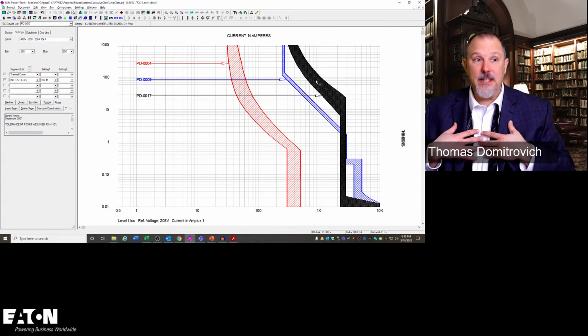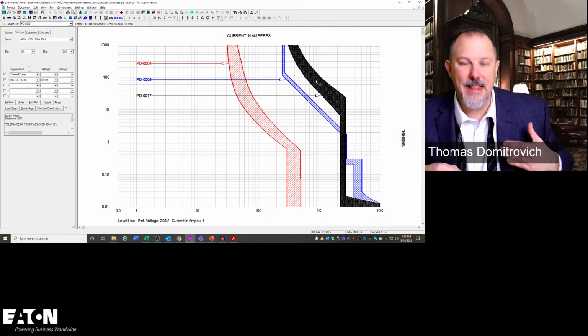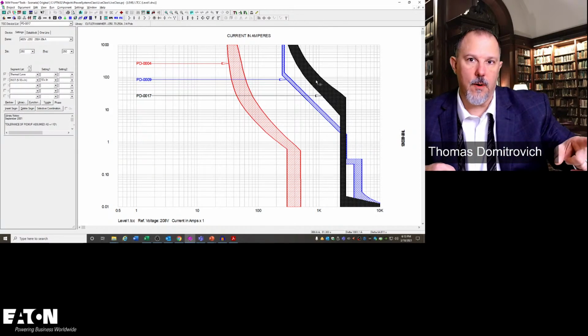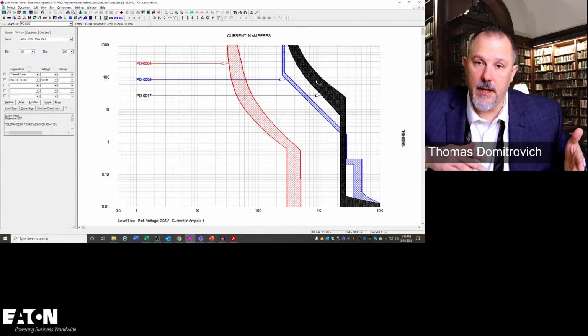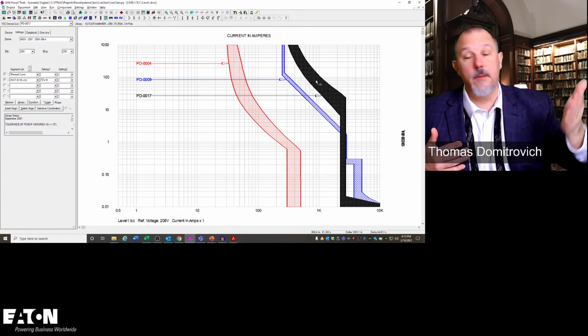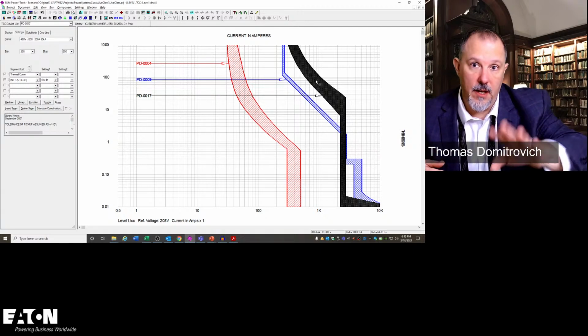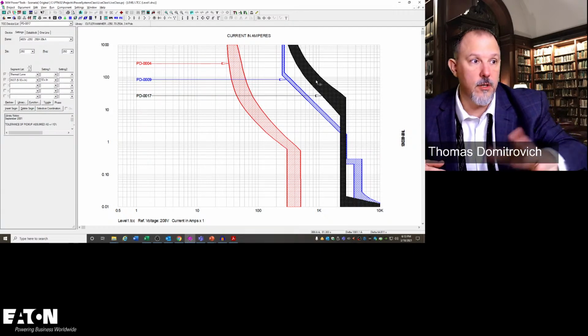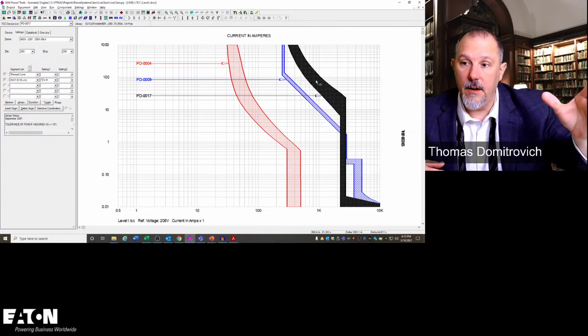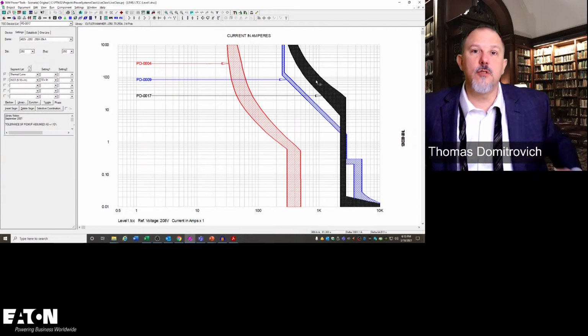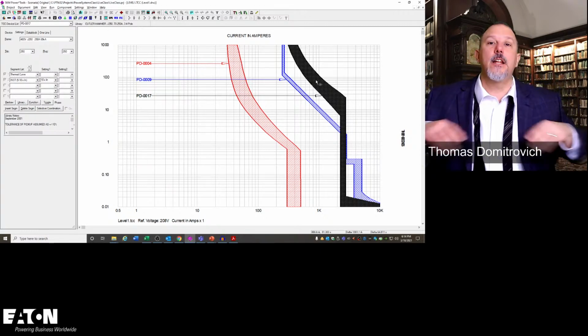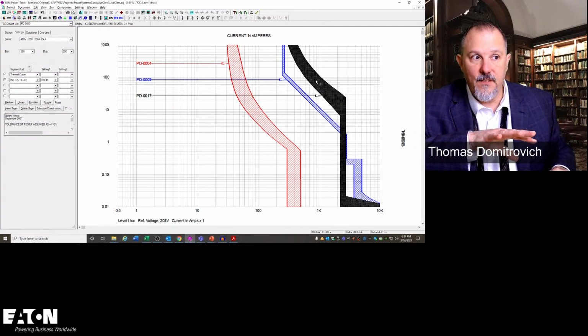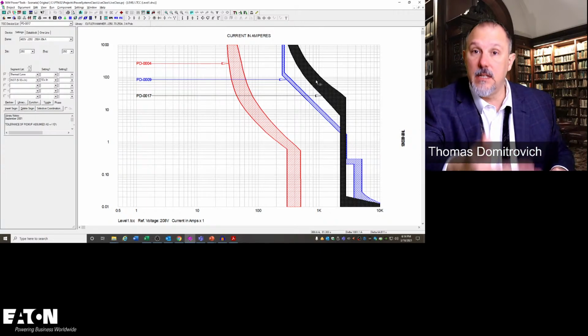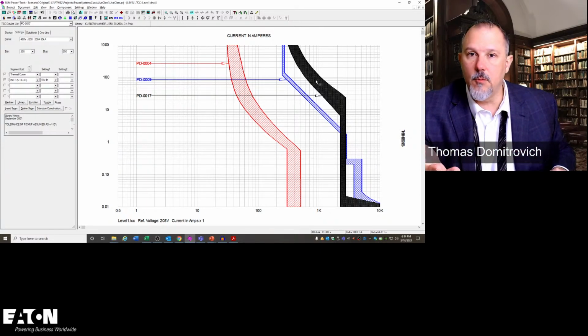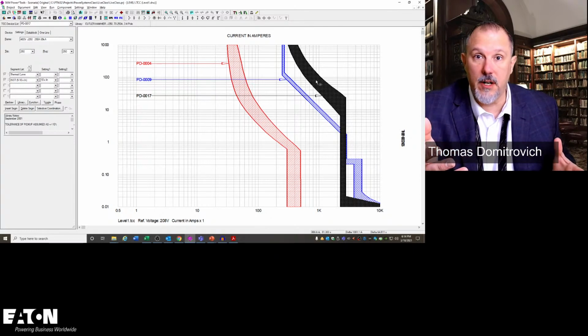Now, what I would typically do is advise my customer. I don't make that decision. If it's not a code requirement, in 0.1 seconds, and it's healthcare, what I would do if it was my project is tell my customer, look, the code does not require you to coordinate to the ground fault current. The code doesn't require you to do any of this stuff. I can ignore it, but if you want a more reliable power system, I would feel comfortable recommending that you coordinate to the ground fault current, because it's the most common fault current in a power distribution system.